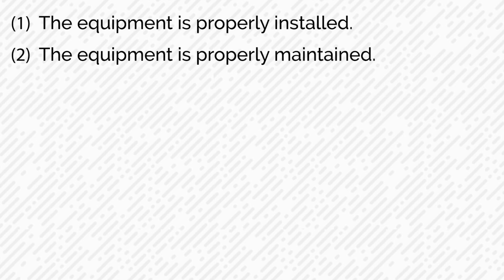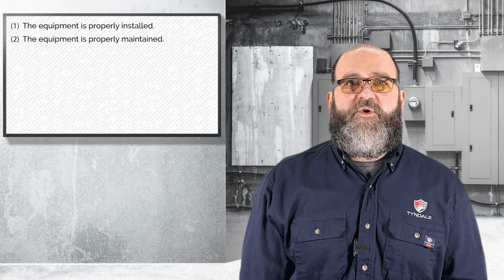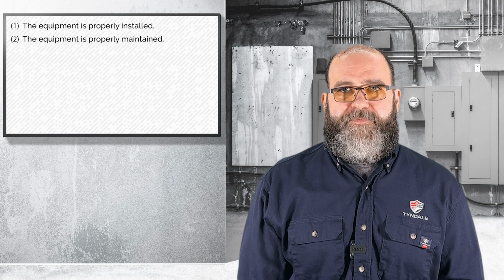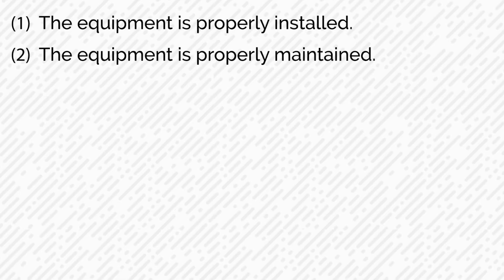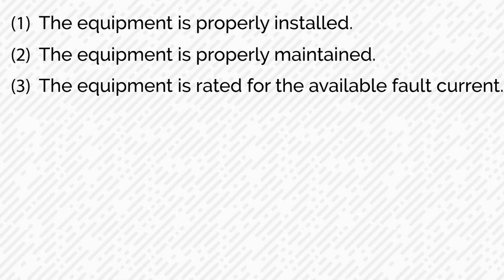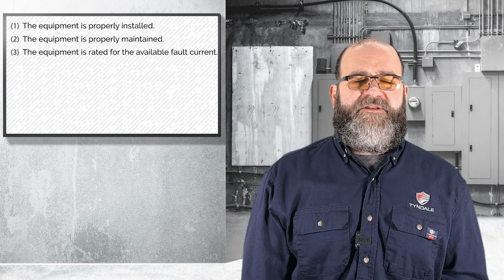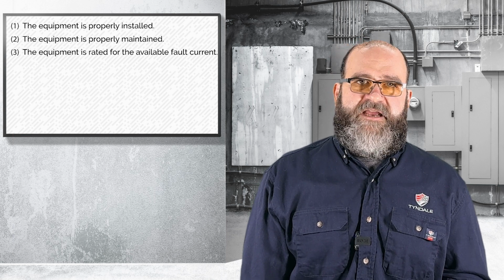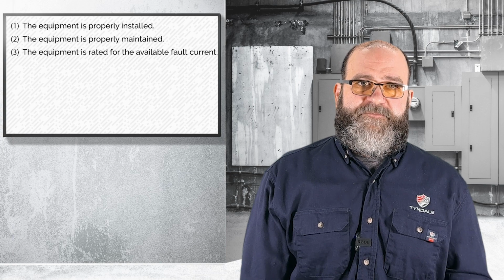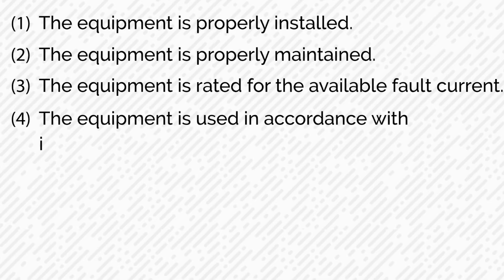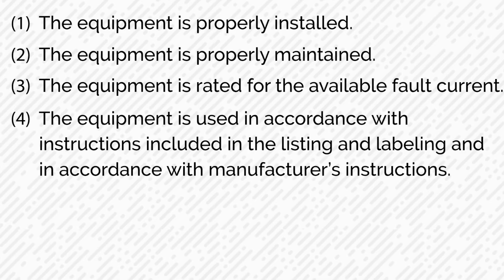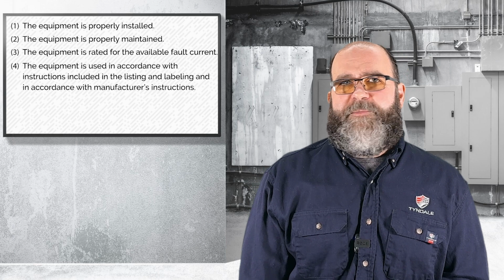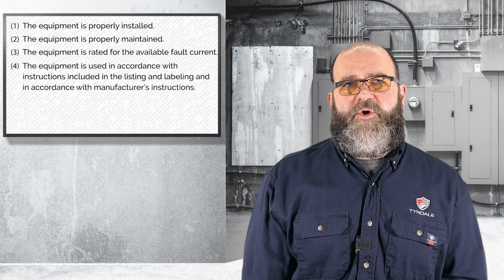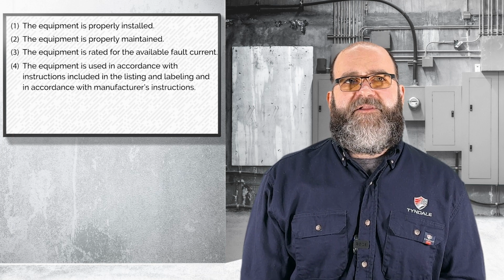Number two, the equipment is properly maintained. That's going to be per the manufacturer, per 70B. I would say that most equipment I've come across is not properly maintained. So right there, you're in trouble. Number three, the equipment is rated for the available fault current. Now, typically the manufacturer, the design, the engineer has designed the equipment for this spec, and that's usually not an issue. Number four, the equipment is used in accordance with instructions included in the listing and labeling and in accordance with the manufacturer's instructions. I would say also typically that's not an issue. I'm sure we've all seen equipment that has been misused, but that's not typically a problem.